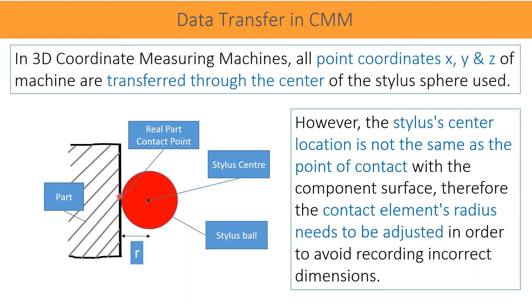In this given figure, point coordinates are measured at the center of the ruby ball, but the actual contact of the ball is here. It is exactly the radius difference. Therefore, the actual point should be moved to the contact surface to get the real part coordinates. This is called probe radius correction or compensation. It happens through the application software logics which will be discussed in the next slides.